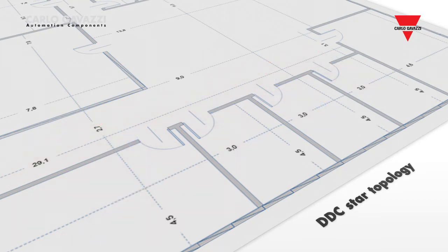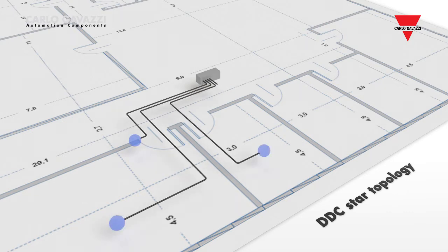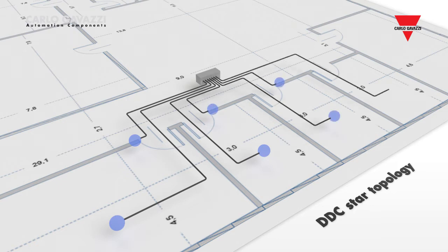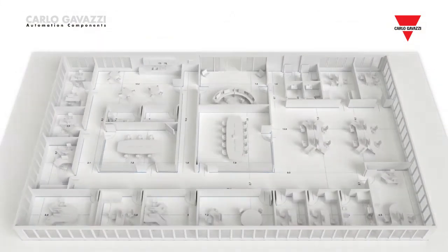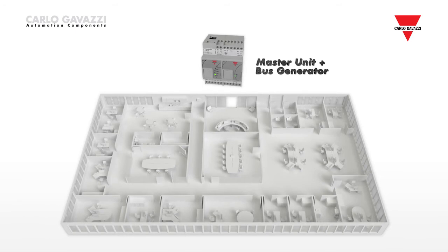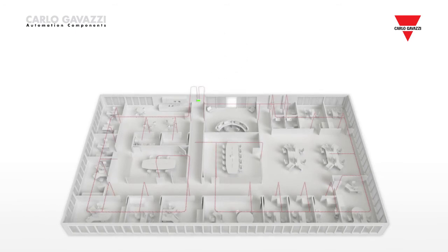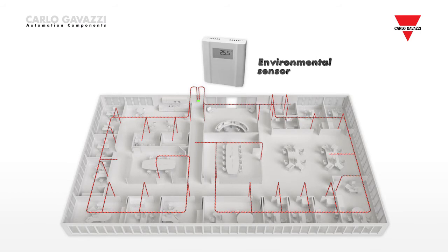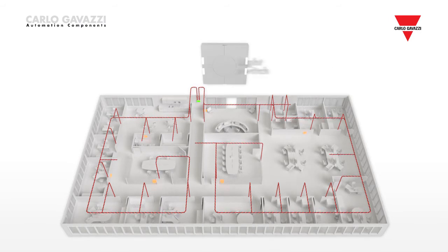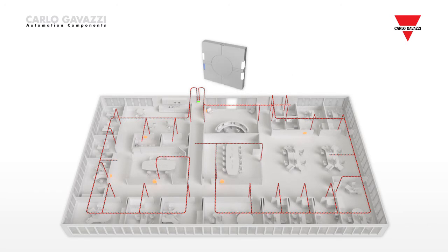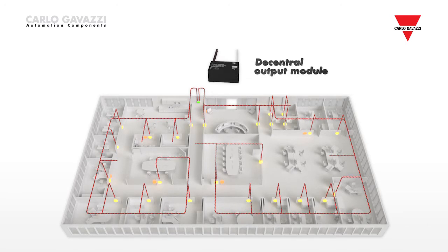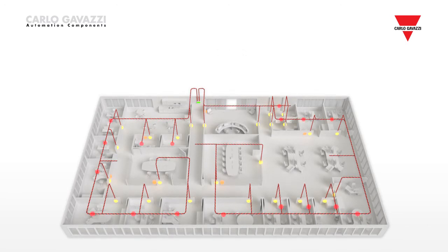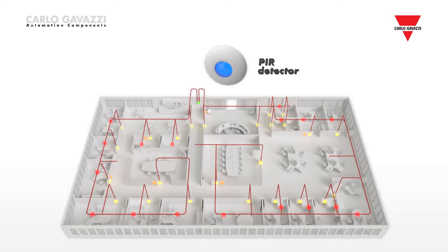In traditional DDC solutions, last-minute changes or future enhancements can be a big challenge. Additional input-output wiring needs to go back to the DDC controller, and there may not be any spare input-outputs or panel space available. The Dupline bus has great flexibility to deal with such situations. The system can easily be enhanced because if additional input-output points are needed, the bus cable can easily be extended and the required modules added. Fewer rules means simplified installation and less risk of time-consuming troubleshooting caused by installation faults.